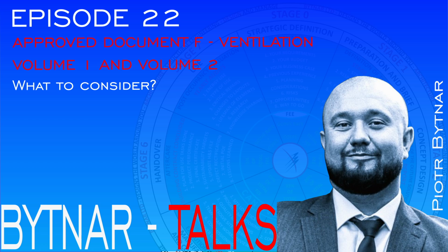Section 1, similar to Volume 1, deals with ventilation provision, different building types, and that's where it differs here, as we have several different building types that we treat a little bit differently. This includes offices and car parks, which have tailored ventilation requirements. Ventilation should avoid mold and pollutants, be properly designed and allow maintenance. Extract, supply, purge ventilation and indoor air quality monitoring are required for certain rooms.